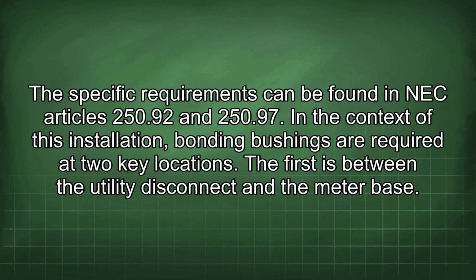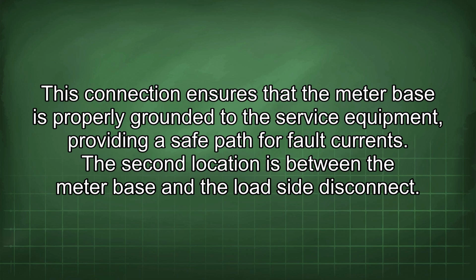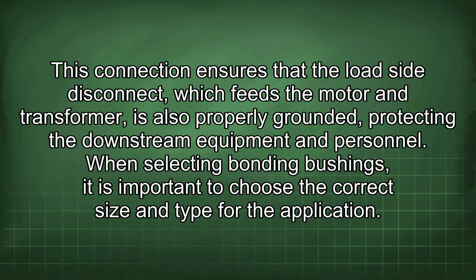In the context of this installation, bonding bushings are required at two key locations. The first is between the utility disconnect and the meter base. This connection ensures that the meter base is properly grounded to the service equipment, providing a safe path for fault currents. The second location is between the meter base and the load side disconnect.